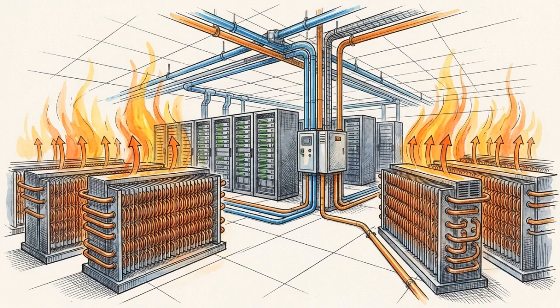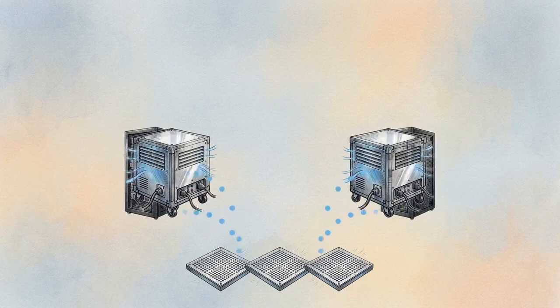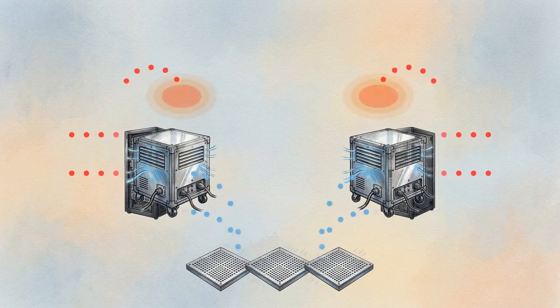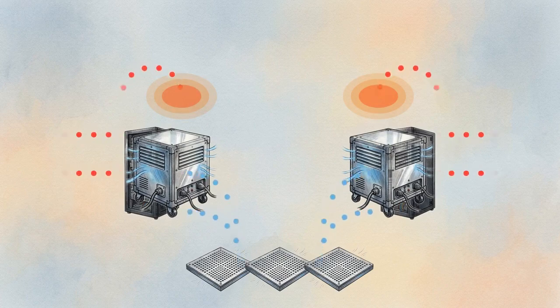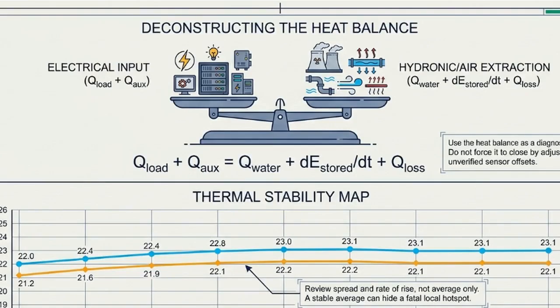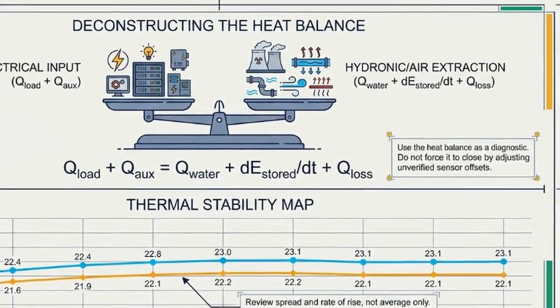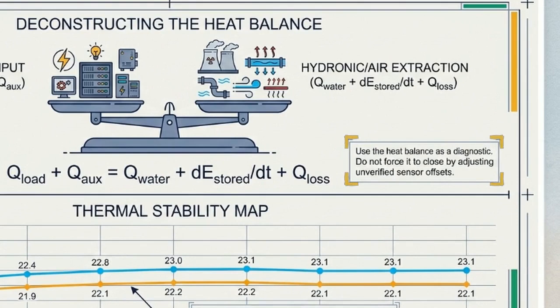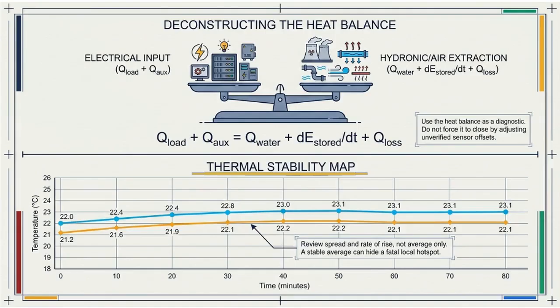This operates as a strict physics experiment, requiring the deployment of server-proportioned electrical heater banks to replicate spatial airflow patterns and intake hotspots. This diagram illustrates the core requirement of heat load testing, mathematically reconciling applied electrical heat against hydronic heat. We prohibit adjusting unverified sensor offsets to force the math to close. The test advances only when thermal stability is proven during the hold period.